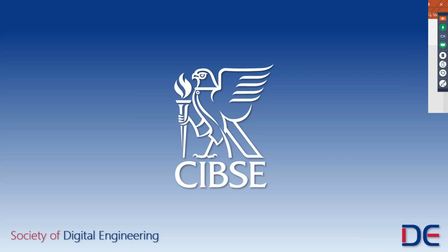That's a very good question. I would add that in as either a factor, or if you have the numbers for the system volume, then that should actually be included within the pipework system. So for example, if we have an LTHW system that is feeding a radiator circuit, the radiator should have a parameter that says I contain this quantity of water, and that should be the same parameter that feeds into the volume within the pipework. Again, it's not a straightforward thing to do, but it certainly can be done.